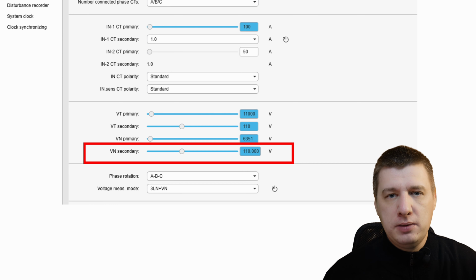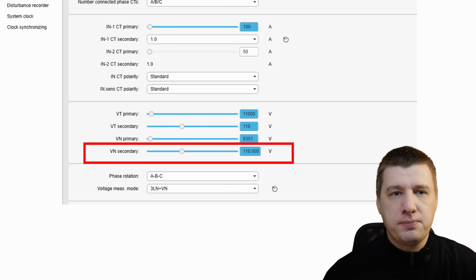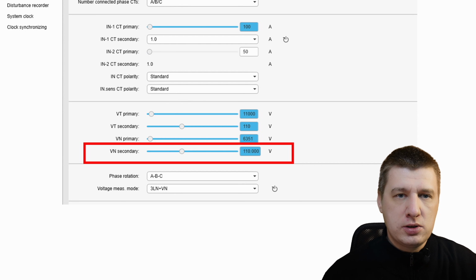VN secondary, an example. Previously we looked at the VN primary, the big picture of neutral displacement in your high voltage network. Now we're looking at the other end of the wire. VN secondary is the voltage the relay actually feels at the terminals, and getting this right is essential for displacement. VN secondary is the rated secondary residual voltage of your voltage transformers. While your main phase voltages are connected to the first few terminals, the residual voltage signal, often from a broken delta, is wired to the fourth voltage channel, specifically terminals A7 and A8 in slot A. Let's use this as an example.